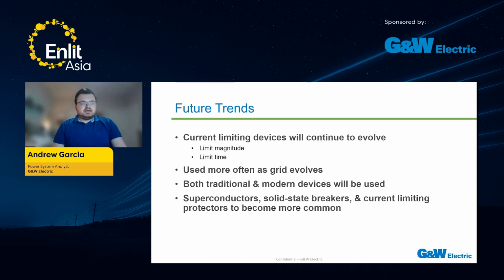New technology may evolve that is not currently in this presentation, and it's important to keep an eye on what's going on in the world. These devices are going to be used more often as the grid evolves and changes. Once again, the grid is undergoing a revolution, as Jimmy put it. As this revolution occurs, fault currents are definitely going to increase, and there's going to be a greater and greater need for a lot of these devices, both traditional and modern. Specifically, we anticipate that superconductors, solid state breakers, and current limiting protectors are going to become a lot more common in the future.